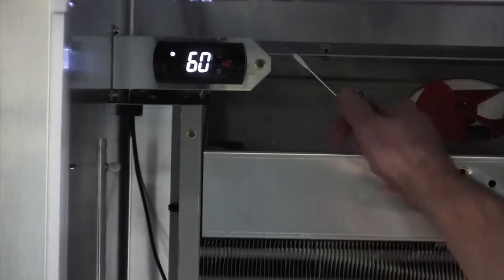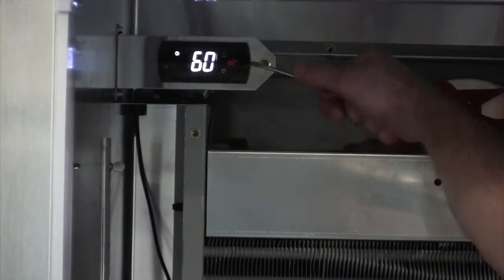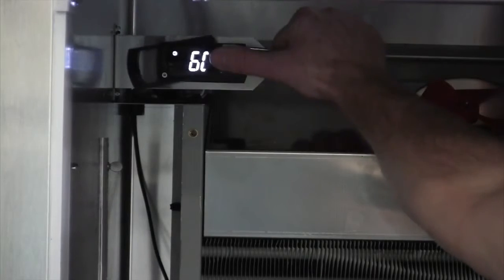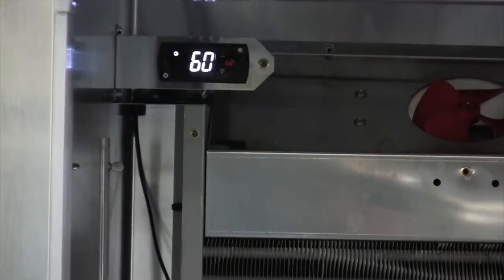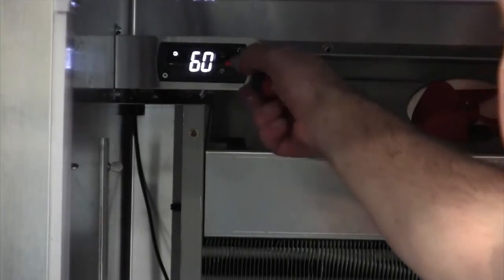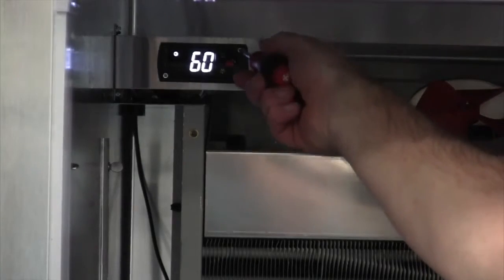To remove the temperature display, use a small flat screwdriver to carefully lift up on the plastic bezel. Then use a number one Phillips and turn the two screws a quarter turn counterclockwise. The display can now be removed.